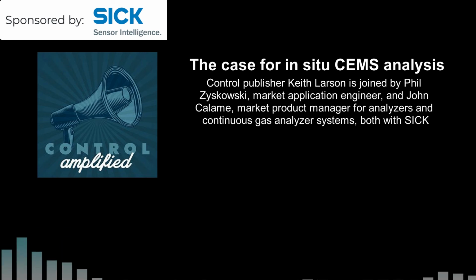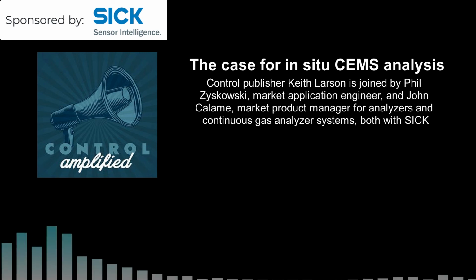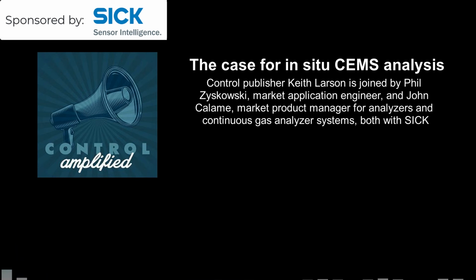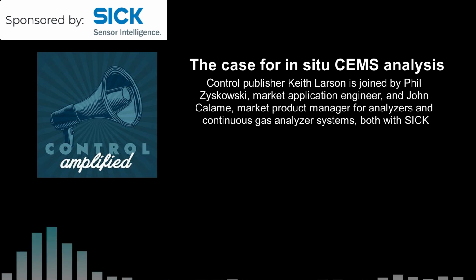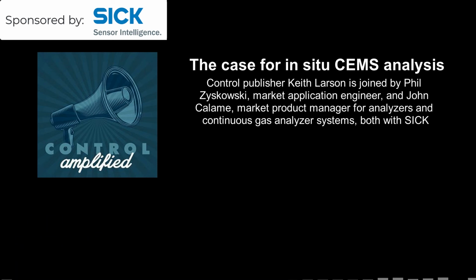Our next approach is always hot-wet. After that, hot-wet is a special, unique construction that we've invented that allows us to take the sample in without having to put it through a chiller. Okay, and so that eliminates a couple of extra pieces that are usually maintenance intensive, right? Water coalescers or chillers that have pumps and filters and things like that. Yeah. And then, finally, if neither of those two approaches will work, then we have the cold dry, which is tried and true. There's familiarity with that, and so that's the way to go.